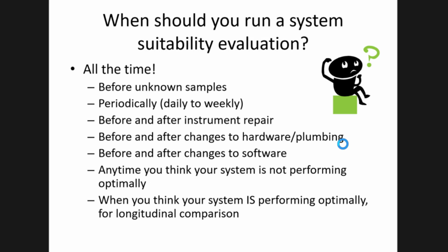Periodically, many times a day, one time a day, it's kind of up to you how long that system suitability run is and how much time it takes away from your sample analysis, keeping in mind that when you have a run that fails system suitability, everything before that is suspect. So if you want to run a system suitability once a week, then you have the option to potentially throw out a week's worth of data that you're not sure if it was performing correctly.